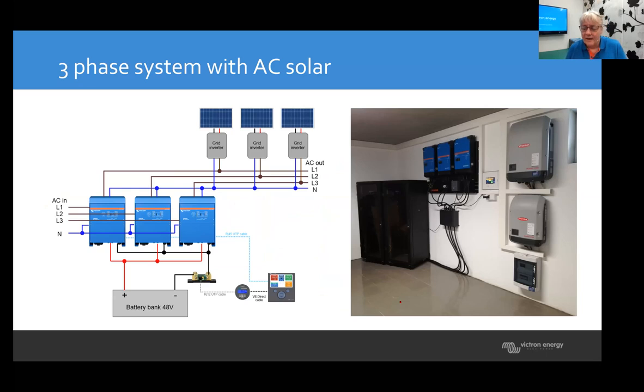If you want to add AC solar, you basically take a big 3-phase solar unit or single ones. This example shows a 3-phase one and a single phase one. You don't necessarily need to balance things out — on average it's good to have a balanced system, but in some scenarios it doesn't matter. They might just put solar on one phase, not on all phases. It can be 3 individual solar grid feed inverters, a big 3-phase unit, or a 3-phase plus a single phase unit as in that example. It's all flexible — again, it's like Lego, you just put together what needs to be together.